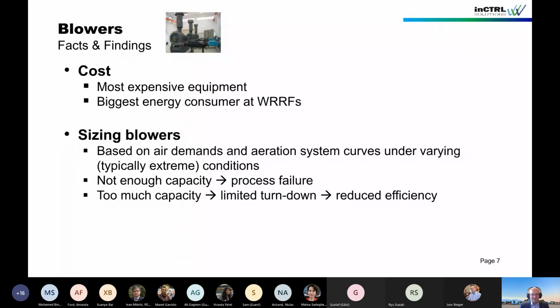Now, in terms of sizing blowers, you really need to take into account the air demands of the system, and how they change over time. You need to be aware of the aeration system curve and how that changes and varies under different operating conditions. And you need to know the blower curves as well, because all those three things interact: the actual performance of the system, how much air you will actually need, and what the blower can supply.